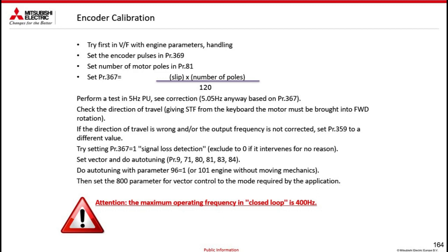And if I see that the frequency fluctuates, the encoder is read. If the frequency remains flat, it means that the encoder is not read, and the causes can be two. Either the sense of rotation is wrong, so you just have to change parameter 359 from 0 to 1, or from 1 to 0, or else you have something wrong in the wiring, and then you have to review it.